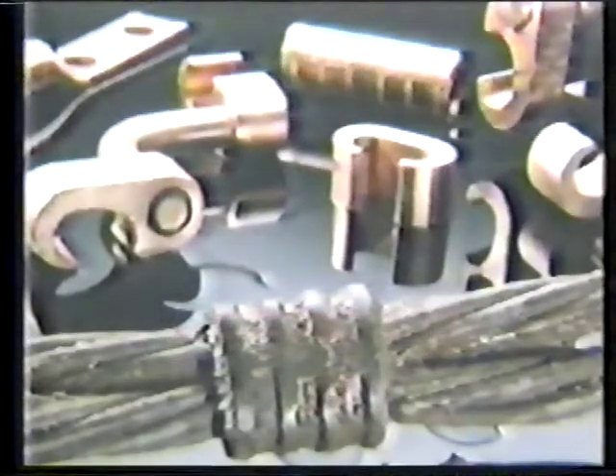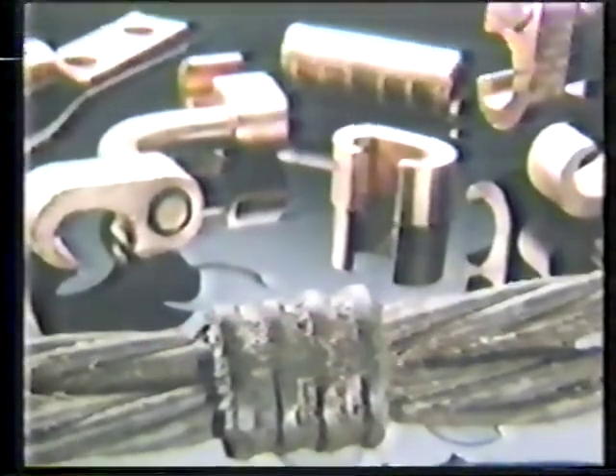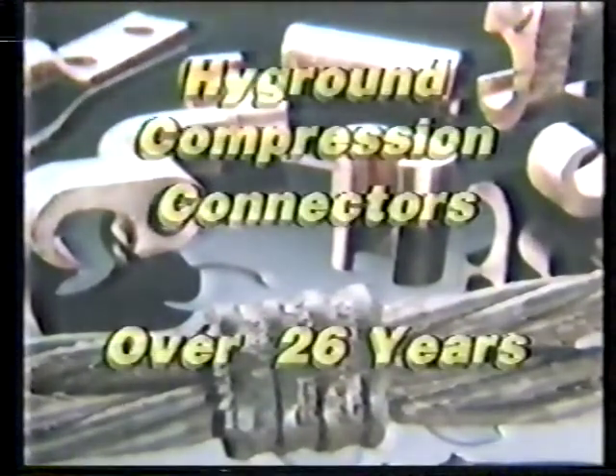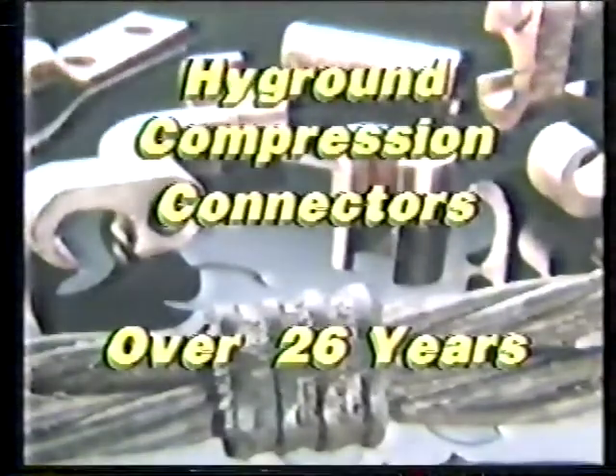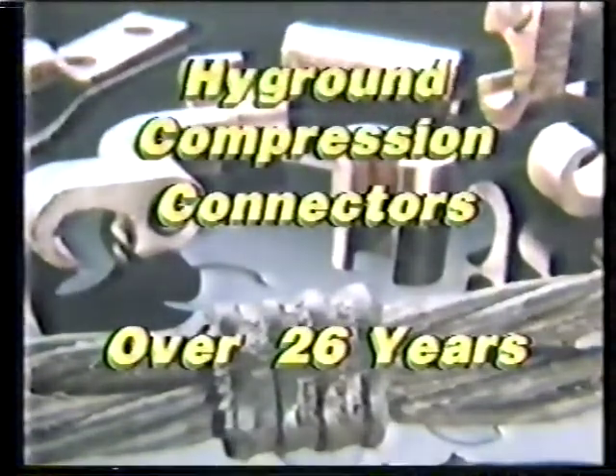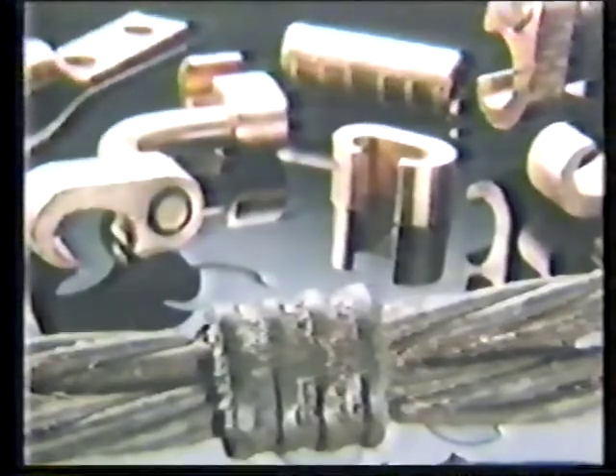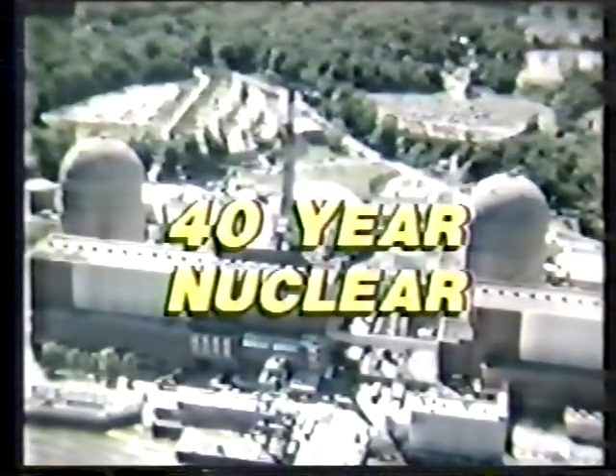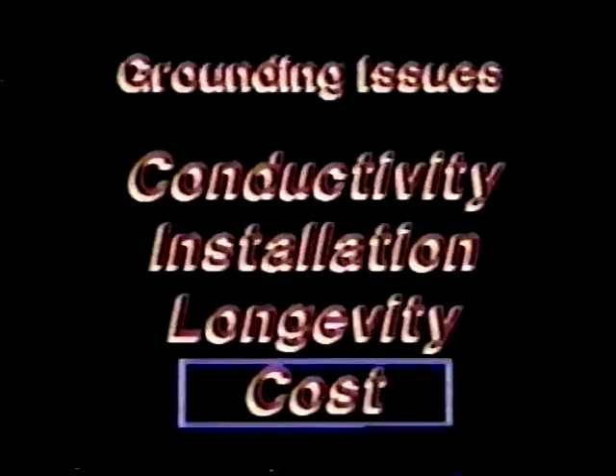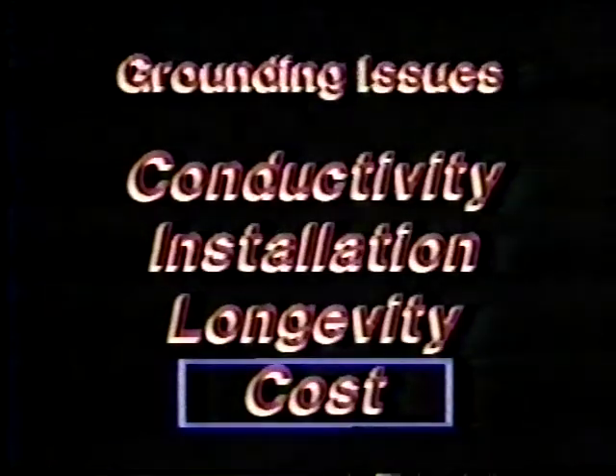In fact, Hyground connectors have been in service for over 26 years, with the test results to prove connection integrity. It's no wonder that they meet all of the latest requirements for IEEE 837, are UL listed, and even meet 40-year life nuclear requirements. When it comes to installed cost, Burndy's Hyground system truly shines.